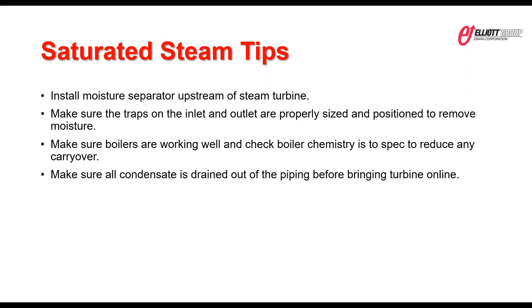One of the biggest things, and this is in every single one of our operator manuals, is that when you start up the unit, you make sure the piping is drained of any condensate, and of course that it's nice and warm before you bring that turbine online.